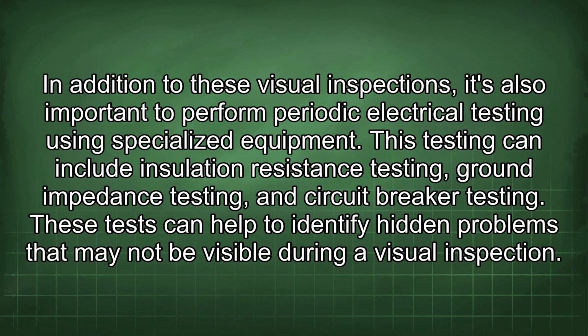In addition to these visual inspections, it's also important to perform periodic electrical testing using specialized equipment. This testing can include insulation resistance testing, ground impedance testing, and circuit breaker testing. These tests can help to identify hidden problems that may not be visible during a visual inspection.